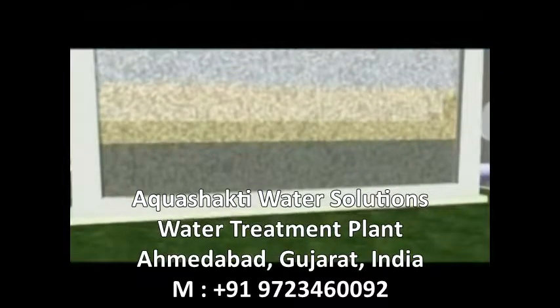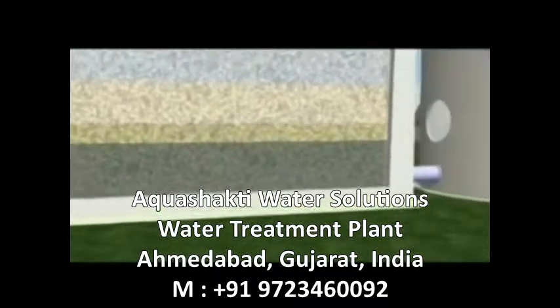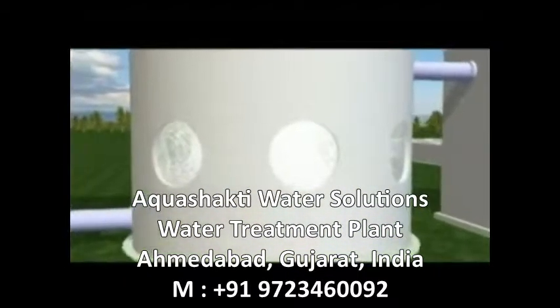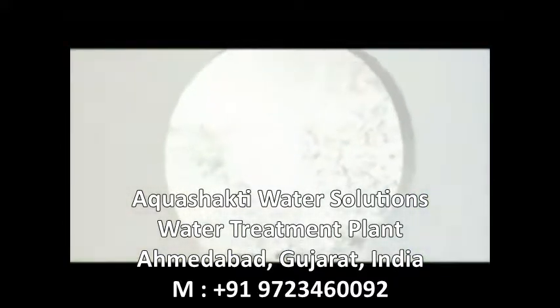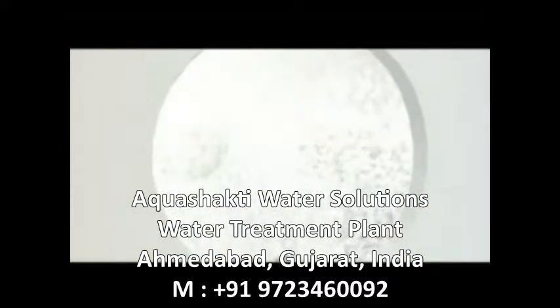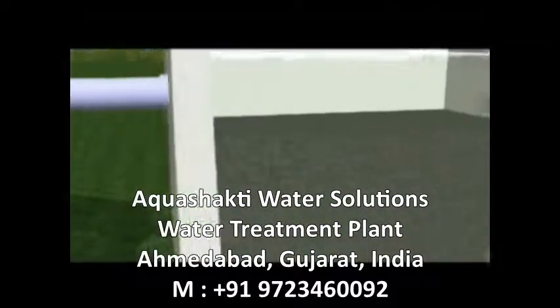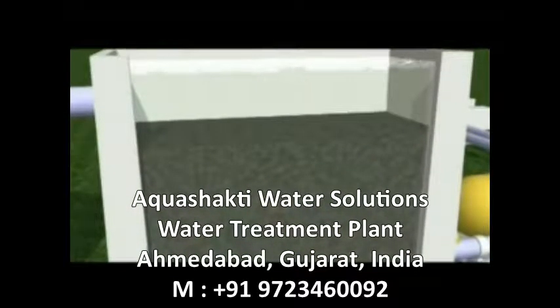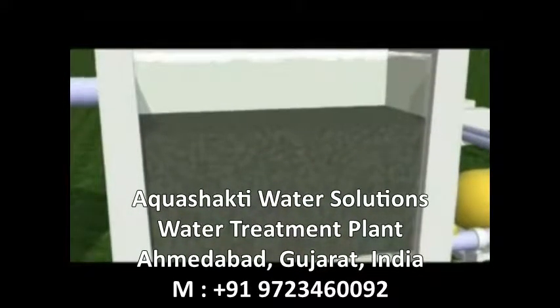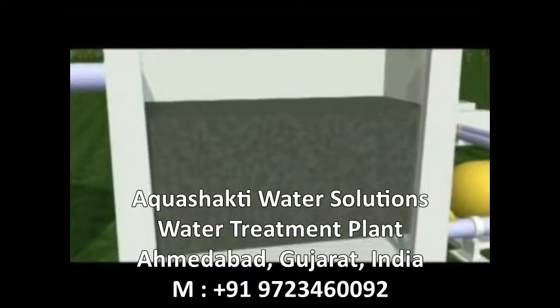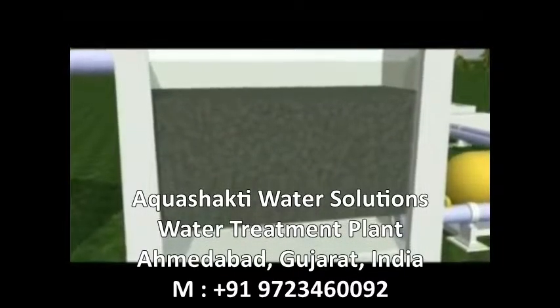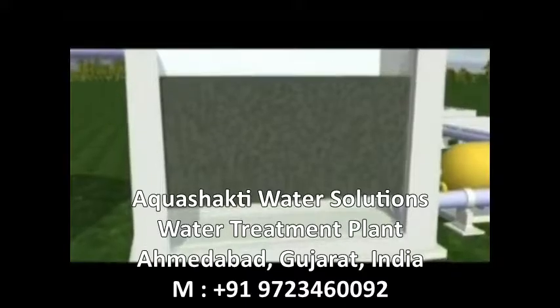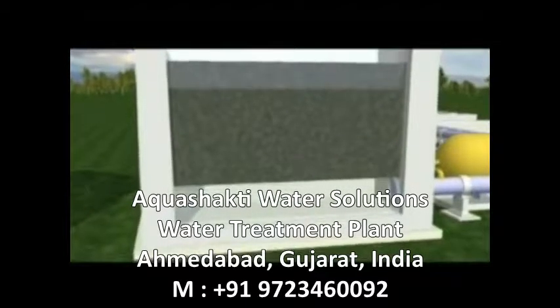For some river waters, we use ozone gas injection as a treatment stage. This can work in conjunction with GAC, or granular activated carbon treatment, where the water is filtered through carbon granules to take out any undesirable traces of largely natural organic materials. The carbon in these filters is removed and regenerated by heat so it can be used again.